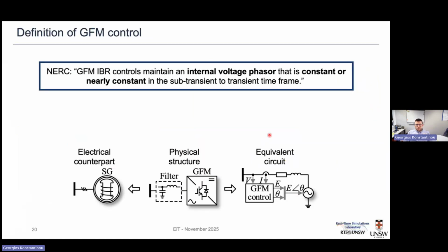So if we try to understand grid forming control, we need to see how to give a general definition of it. Working with the initial definition from NERC in the US — a very similar definition is also adopted here in Australia by AEMO — grid forming control is a control that allows us to maintain an internal voltage phasor, linking to the voltage waveform stability we saw earlier for a strong or weak grid, that is constant or nearly constant in the subtransient or transient time frame.